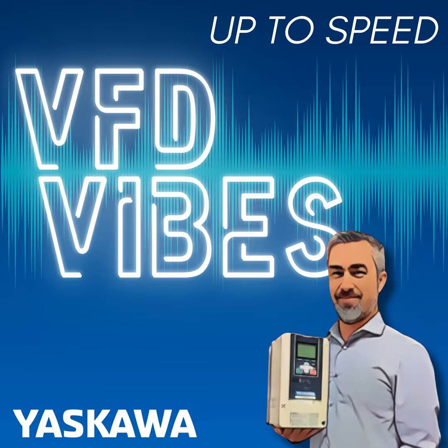So sometimes we'll get quote requests saying, hey, I have a 230 volt motor. I need a drive with bypass. Send me a quote. Now, I'll go back to the customer and I'll confirm with them, is it 208 volt three phase or is it actually 230, 240 volt three phase? Those are two very different power sources, even though they're in the 200 volt class drive. If it's a standalone drive, it doesn't matter. That drive will handle that variation in voltage, no problem there.